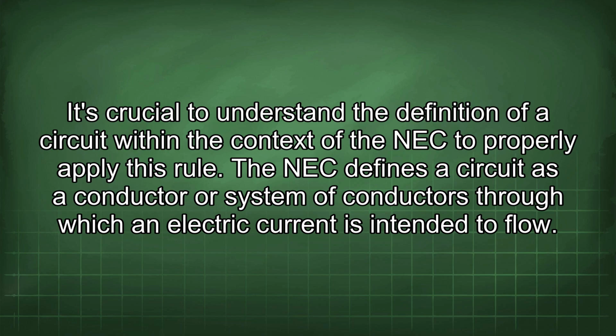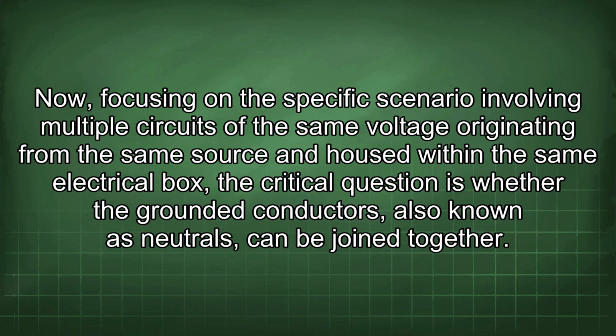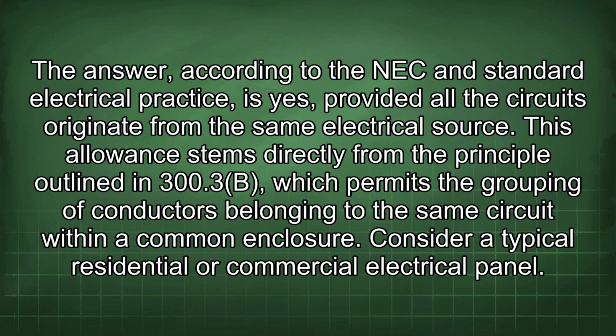Now, focusing on the specific scenario involving multiple circuits of the same voltage originating from the same source and housed within the same electrical box, the critical question is whether the grounded conductors, also known as neutrals, can be joined together. The answer, according to the NEC and standard electrical practice, is yes, provided all the circuits originate from the same electrical source. This allowance stems directly from the principle outlined in 300.3b, which permits the grouping of conductors belonging to the same circuit within a common enclosure.